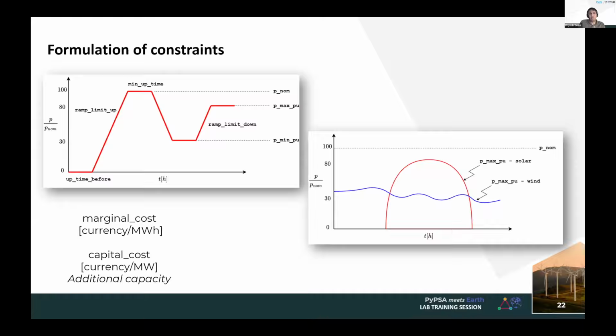So if a plant is going to go from 50 to 100 megawatts in 1 hour, then the ramp limit up is 0.5. So 50% of it can be changed in one hour. In the case of P max PU, that's the maximum power per unit, so the fraction of the power out of the plant's output.